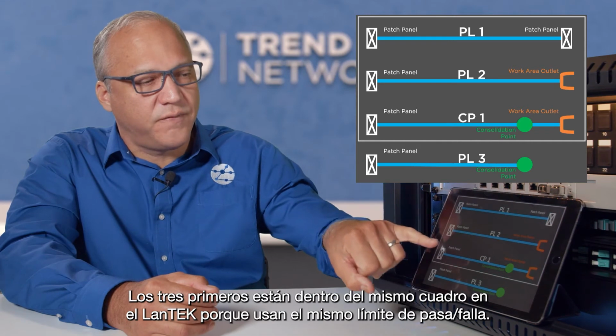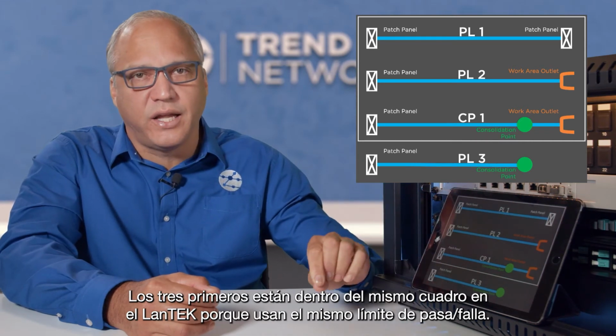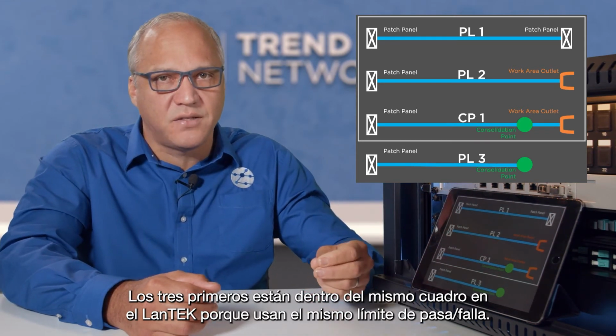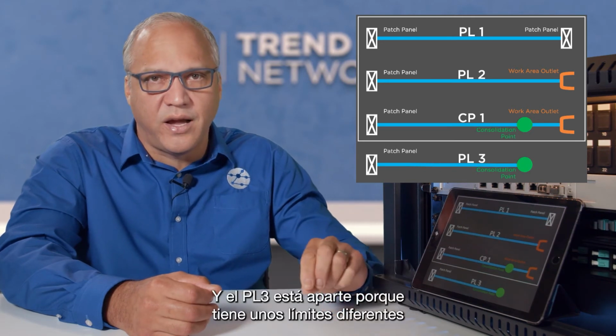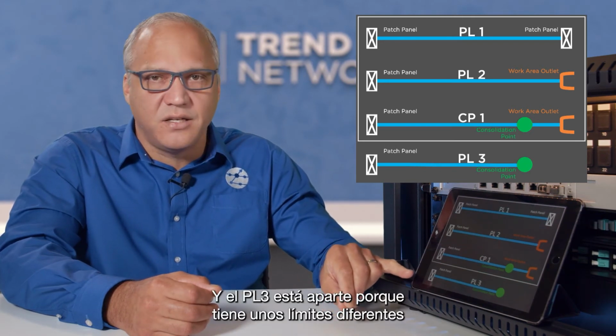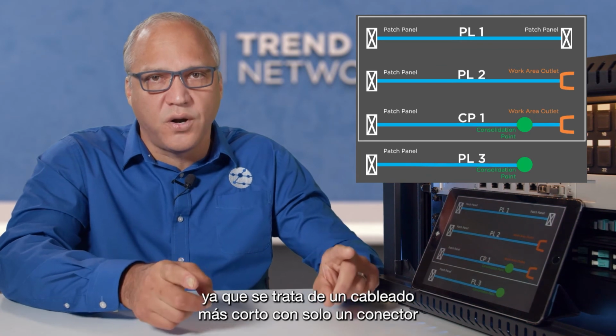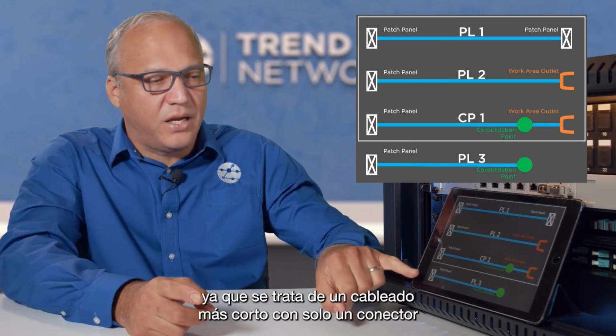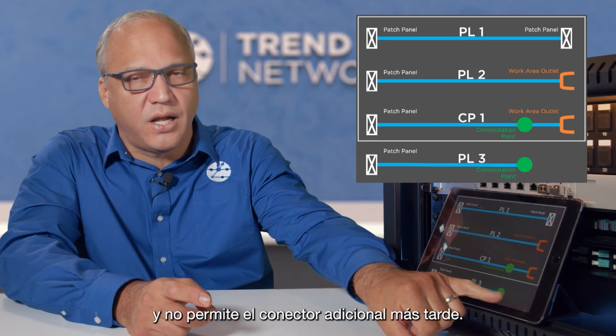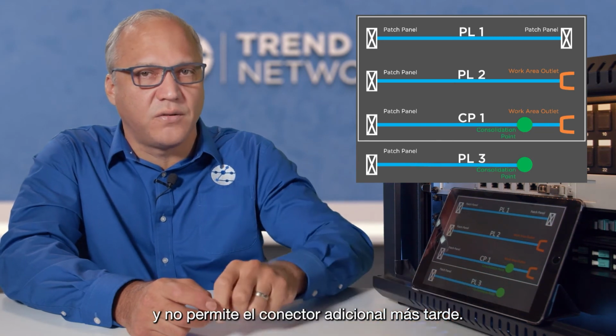So these first three are on the same line in the LanTEK because they all use the same pass-fail limit, and the PL3 is in the line by itself because it has a different set of limits, being that it's a shorter cabling and that there's just the one connector and not allowing for the additional connector later on.